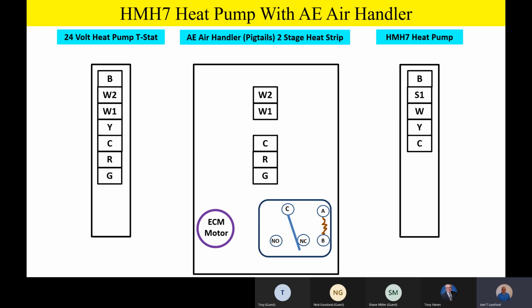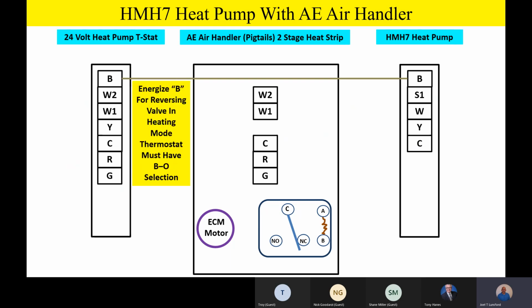So starting at the thermostat, we're going to take that B terminal from the thermostat and take it straight outside. Now remember, team, that B terminal is going to be energizing the reversing valve in the heating mode of operation. Another way of thinking about it is that the default mode on the HMH7 is cooling mode, and you're going to energize the reversing valve in the heating mode of operation.